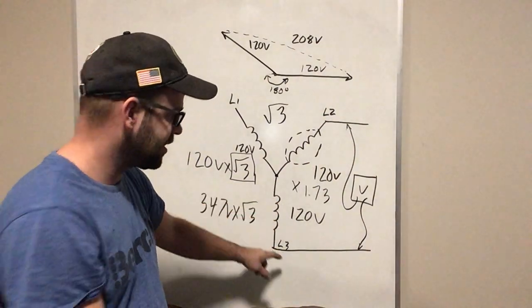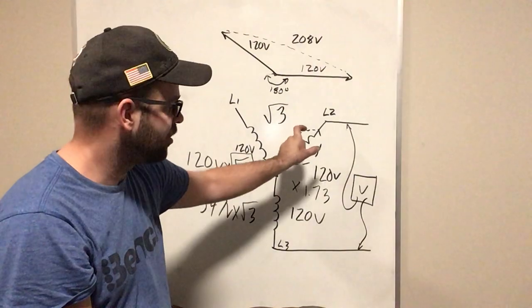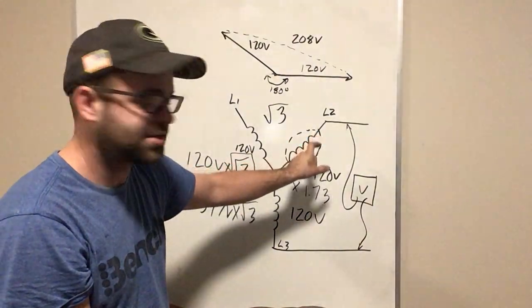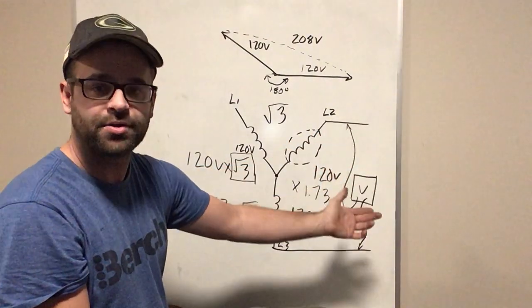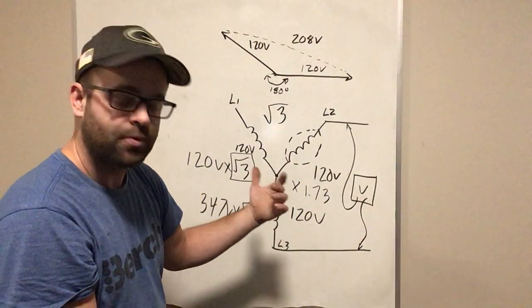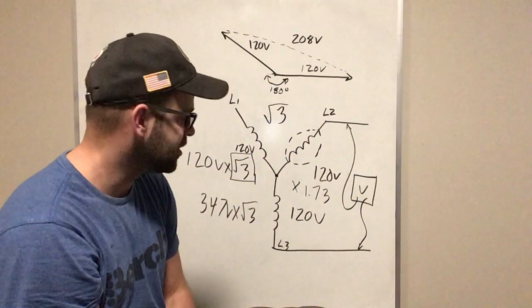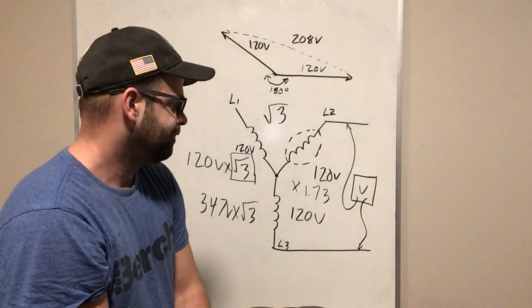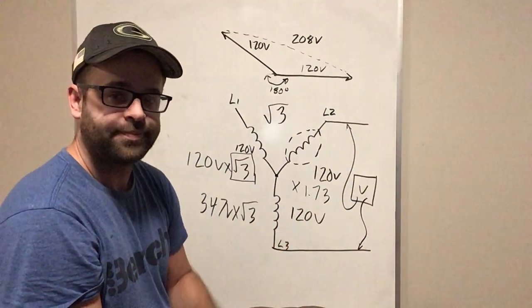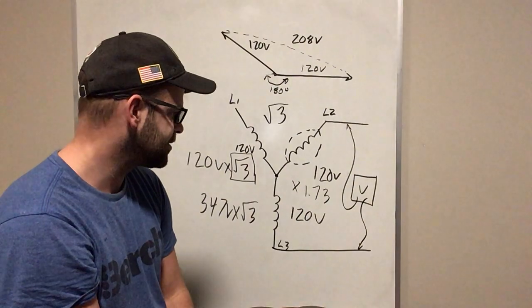But if you look and say, oh, my meter's measuring 2 different coils that are producing that voltage, then my value has to be a larger value. It has to be bigger. And how much bigger is it? It's root 3 larger, because those 2 phases are 120 degrees apart. So that's for voltage. And then I'll just do a little summary when I'm done here with this, with formulas.